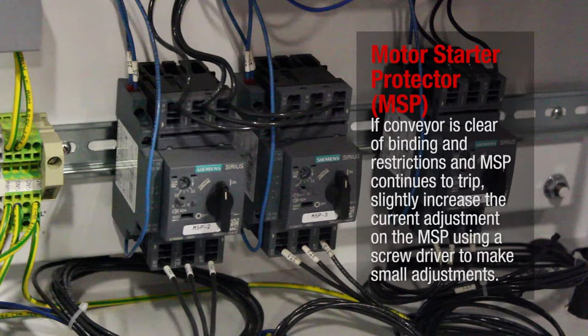If the conveyor is clear of binding and restrictions and the MSP continues to trip, slightly increase the current adjustment on the MSP using a screwdriver to make small adjustments.